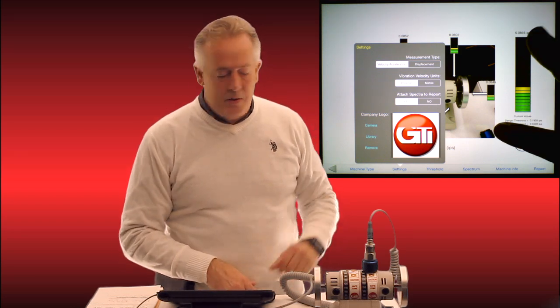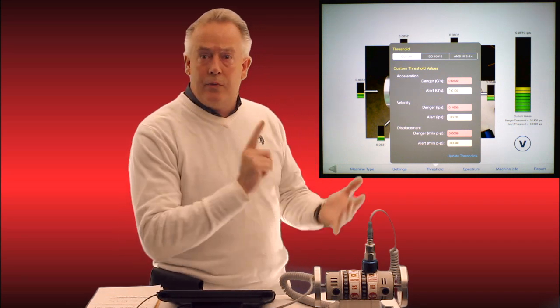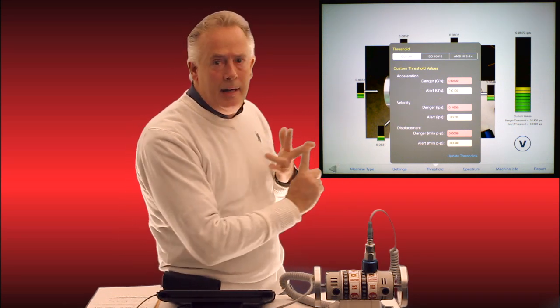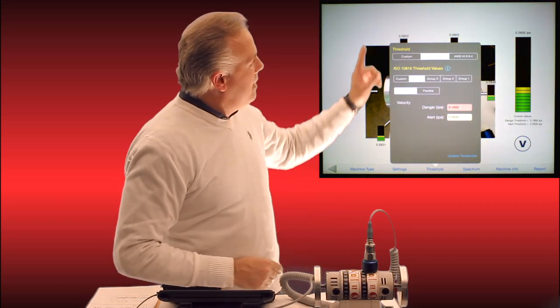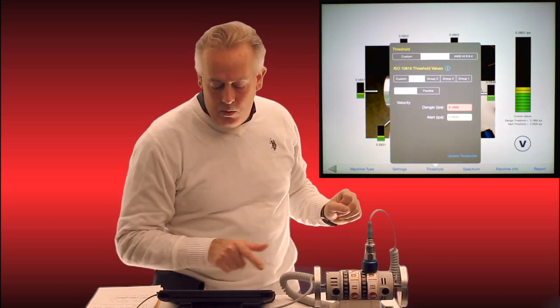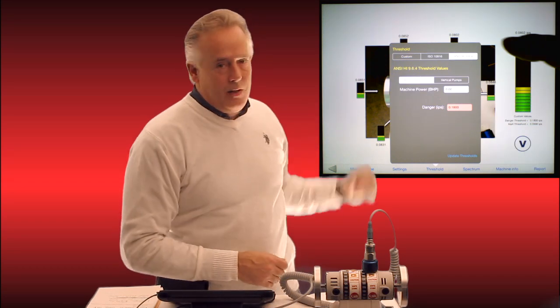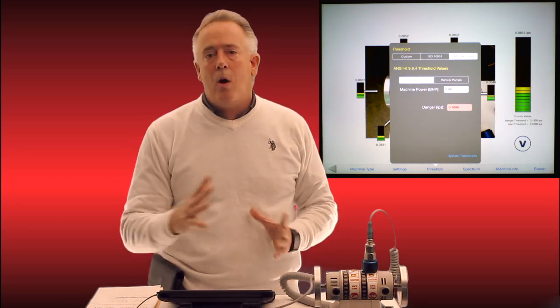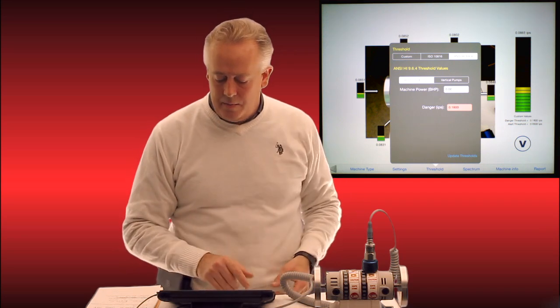Under thresholds, I can set danger and alert thresholds for acceleration, velocity, and displacement — all three modes. At the top I can default to ISO 10816 or ANSI specifications by simply toggling to them, which automatically populates those thresholds. Or I can put in my own custom thresholds.